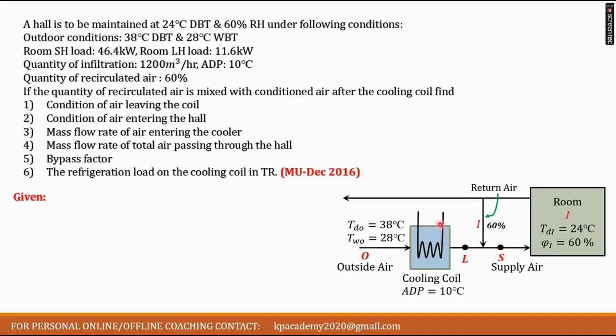Based on this we have to find out the condition of air leaving the coil. That means the L point that we have to find out. Then the condition of air entering the hall, the supply condition, we have to find out. The mass flow rate of air entering the cooler, that means how much mass of that outside air is required to pass, right? The mass flow rate of total air passing through the hall. What is the mass flow rate of supply air? The bypass factor of the cooling coil, and the refrigeration load on the cooling coil in tons of refrigeration. So the tons of refrigeration of this cooling coil we have to find out.